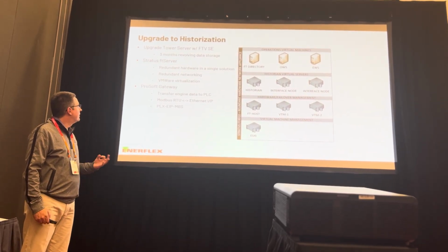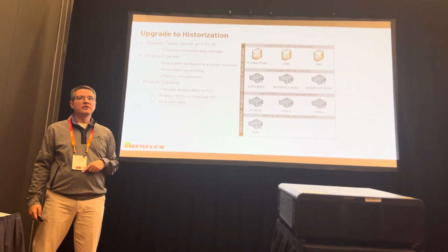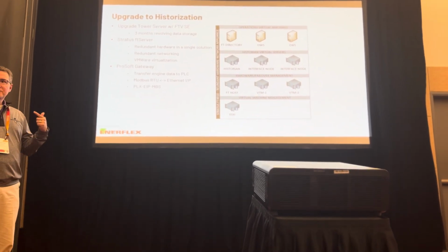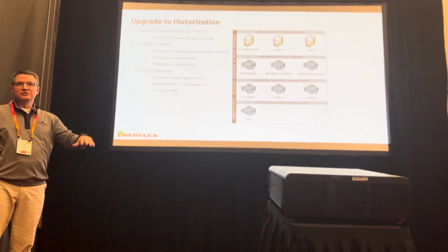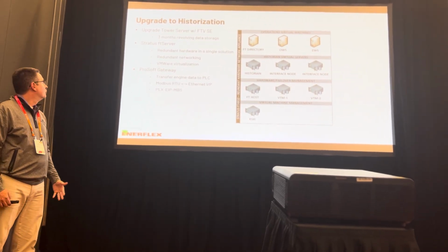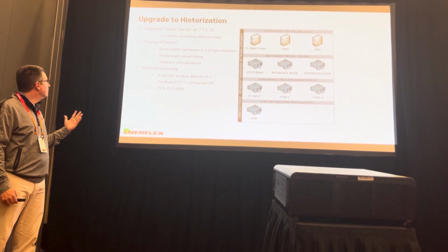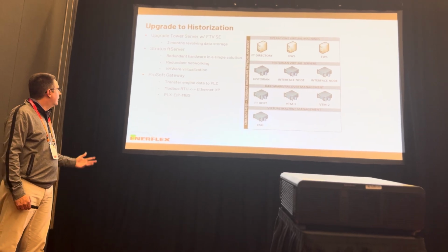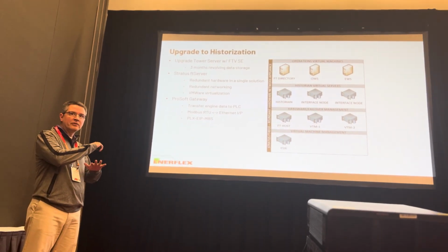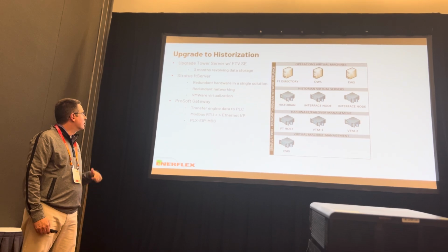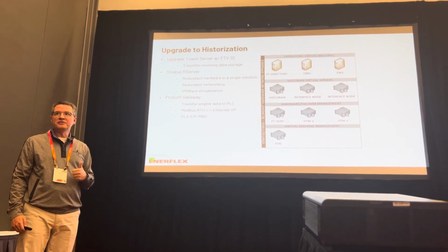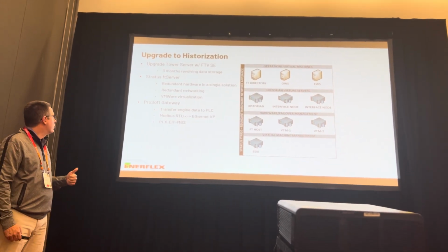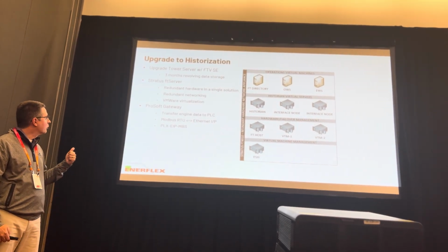So we did this in kind of 3 pillars. The first was we had to do an upgrade to the historian and how they historize data. They had just the desktop class tower machine, which is just doing about 3 months of circular data. So we upgraded that to Historian Server SE, and we used Stratus FT Server, which was mentioned, the dual server mount, the rack mount. And that gave us the redundant hardware. So we wanted to reduce that downtime. They had good downtime to begin with, but we wanted to maintain that, if not get better. So we went with Stratus for the FT server, so the redundant hardware.